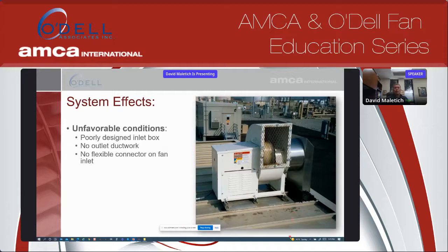Here we have a fan that's exhausting fumes from a lab, top of a portable lab structure. They have isolators. Isolators are nice because they prevent the vibration of the fan, sound of the fan from being transmitted back into the building. However, there's no flex connector here. So the fan is functionally pipe bound to the ductwork. So while noise isn't being transmitted here, it's being transmitted through this duct back into the building to the hood. And so consequently, they're not really saving anything by putting the fan on isolators.